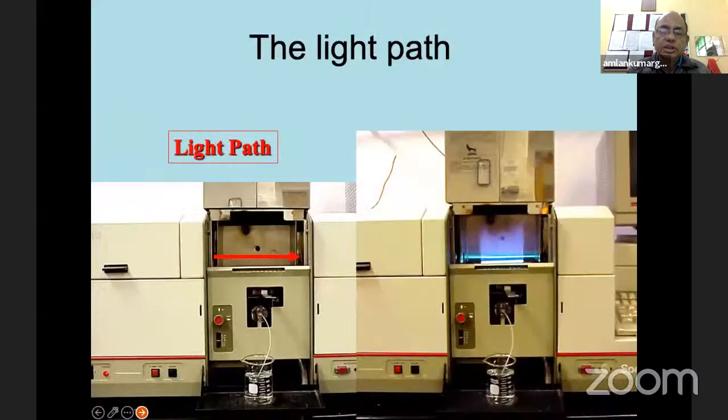If you see next, here this instrument is not working. Here the instrument is working. So you will see that light is coming through this one, and this is the flame. So here you have the sample introduced into the flame and the light passing through the flame.